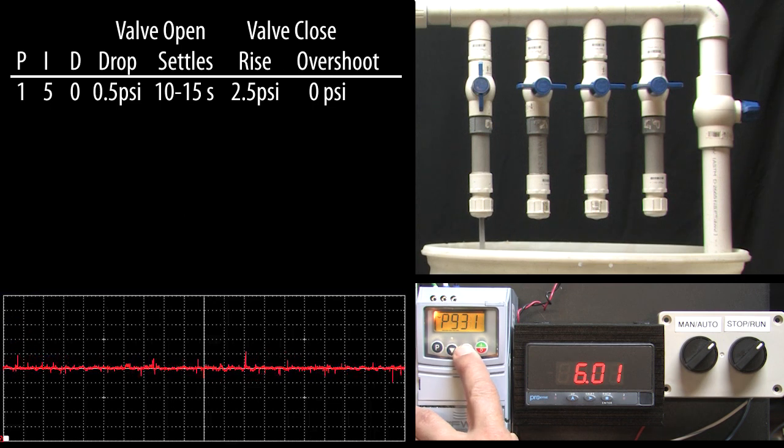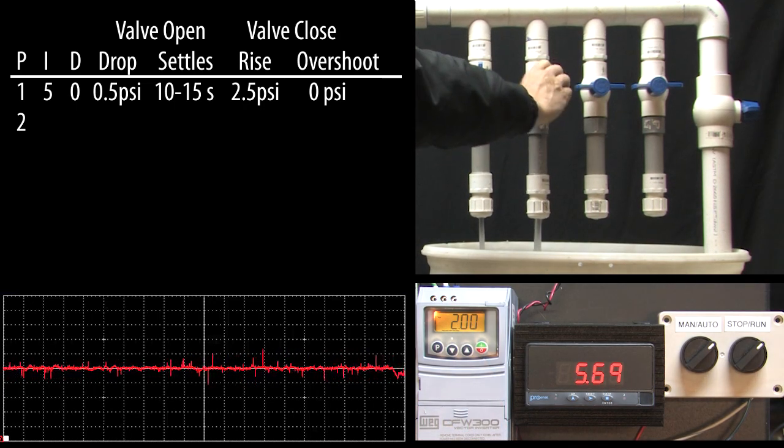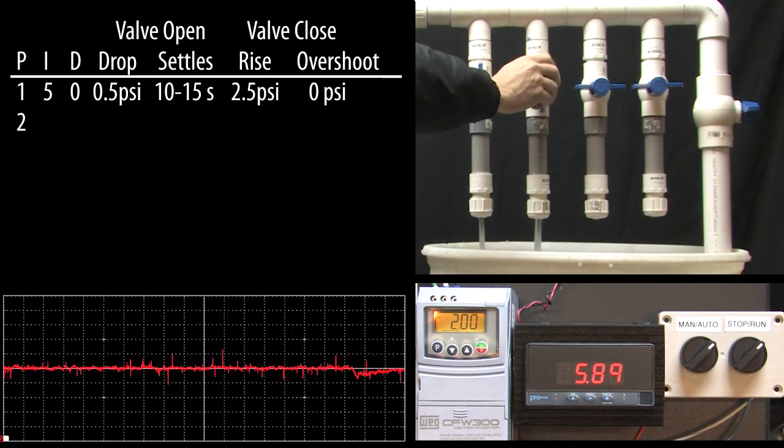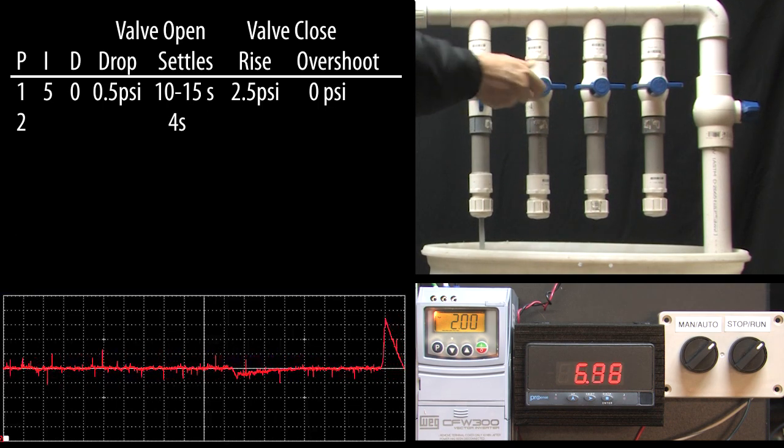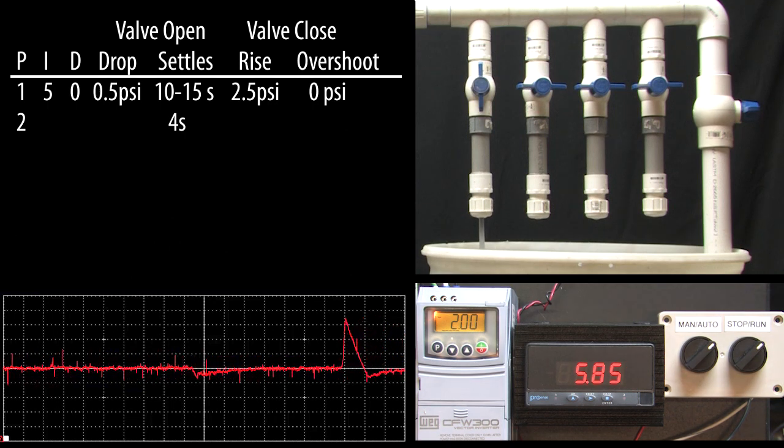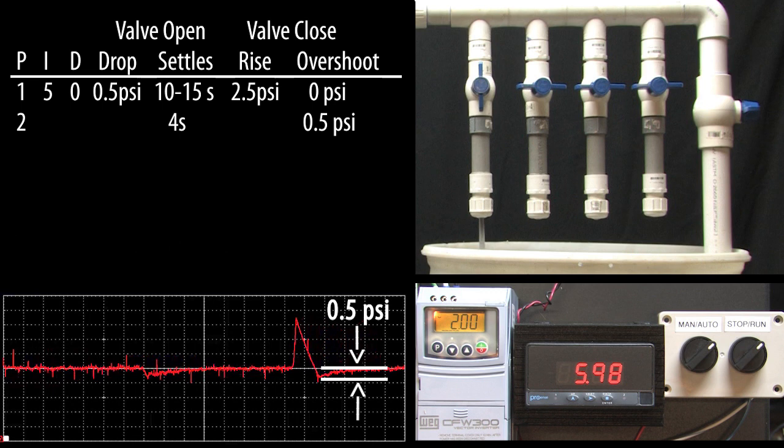The gain is in parameter 931 so let's double that to a 2. Now if I open that same valve, we have a much faster recovery time. Cool! But when I close the valve, the recovery drops past 6 psi by about half a psi so now it takes longer for the valve closing to recover.